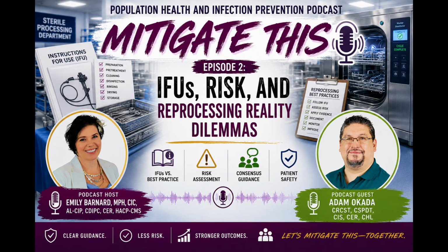You can't just say, well, this is the way we've always done it. That's not going to work with a surveyor. It should not work with an infection preventionist who's coming through sterile processing to audit. There is a right way to do things, and it's from the instructions for use. Remember, though, that's how the instrument was validated to get through the FDA.